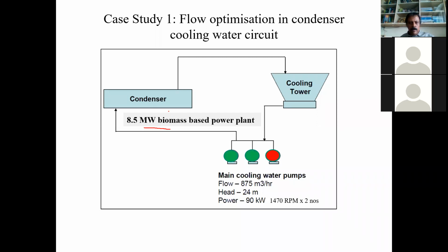So you have a turbine and condenser. The turbine is discharging the steam into the condenser. On the other side, we have the cooling water circuit. The cooling water is pumped to the condenser, goes to the cooling tower, and the cold water again comes back to the pump and is sent to the condenser. This is the system. The pump is a 90 kilowatt pump with 1470 RPM. These are the characteristics, the nameplate rating of the pump.